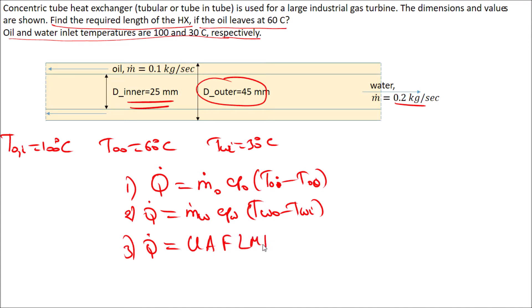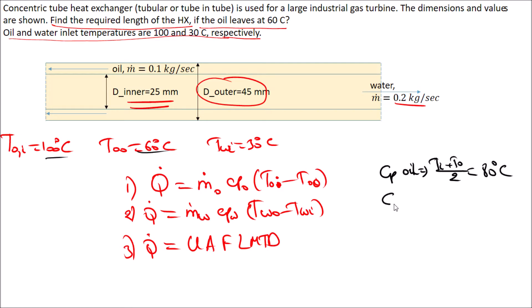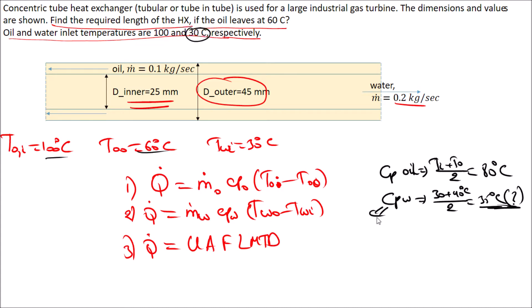First we need Cp values, which require average temperatures. For oil, the average temperature is (T_inlet + T_outlet)/2 = (100 + 60)/2 = 80°C. For water, we don't know the outlet temperature, so we assume an average of about 35°C — assuming inlet 30°C and outlet around 40°C. We will verify this assumption at the end. Cp of water doesn't change much with temperature, so the values will be acceptable.